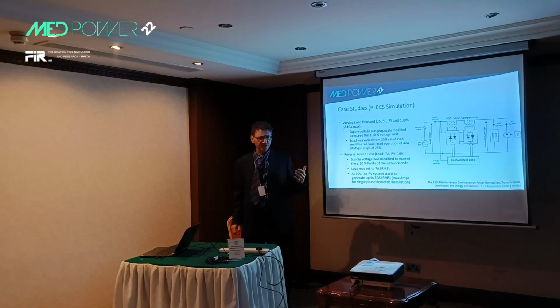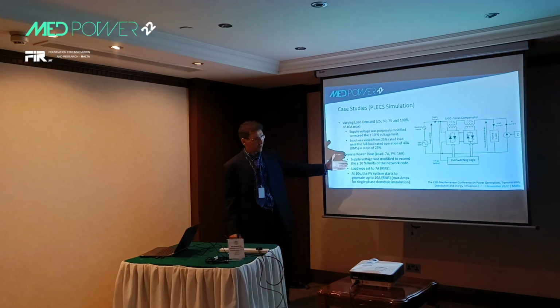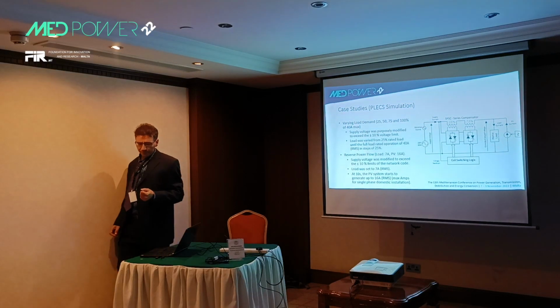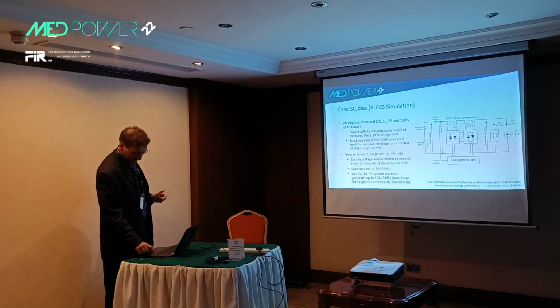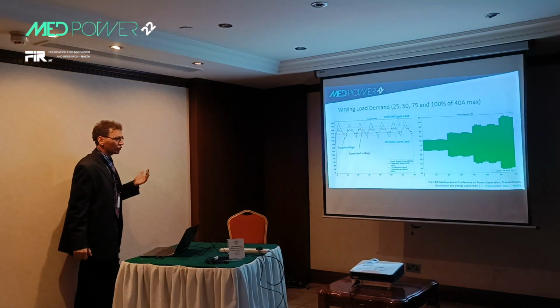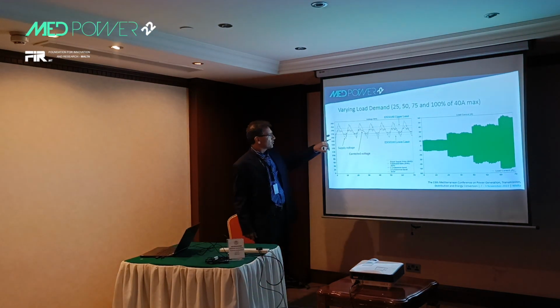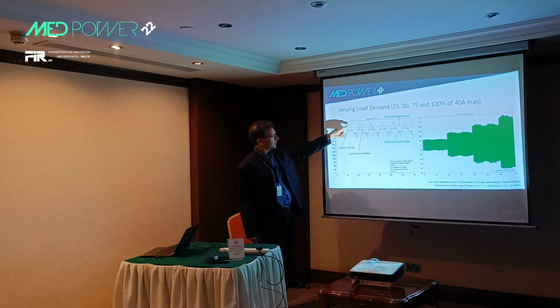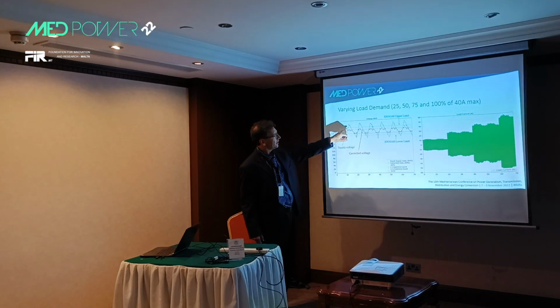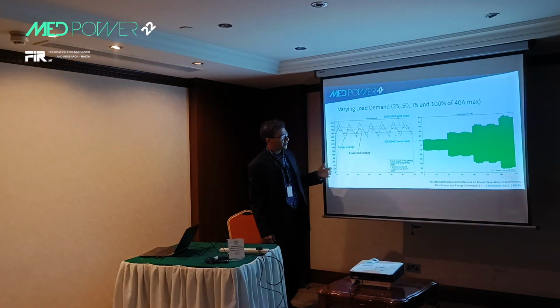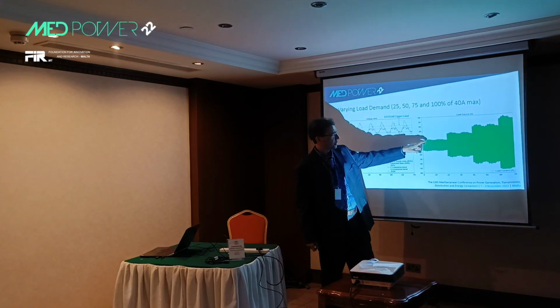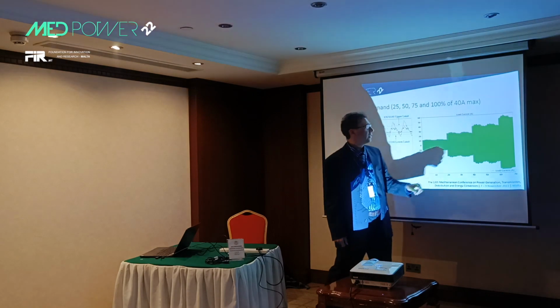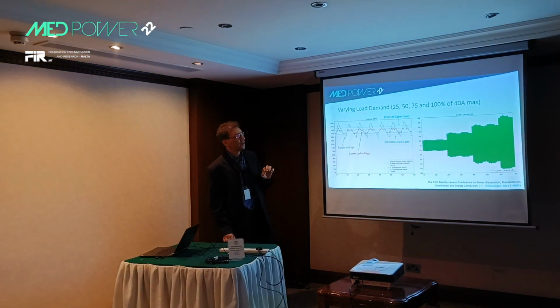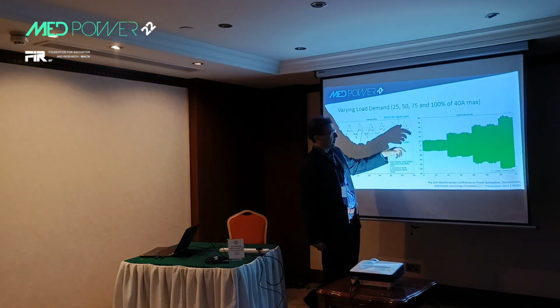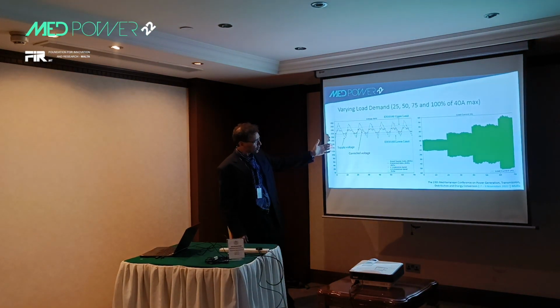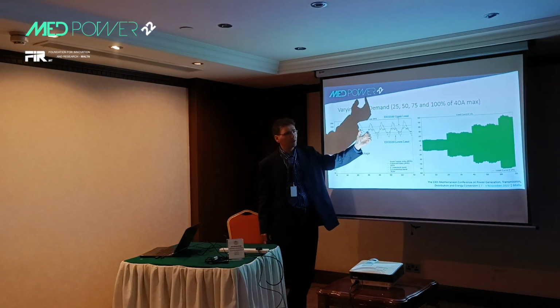And we noticed that in both cases, when we've got heavy loads, when we've got reverse power flow, the compensating circuit and the logic behind it worked in such a way that they always managed to keep the voltage within the limitations. So this is our distorted supply voltage, the green one. This red one is the voltage corrected by our series compensator. Okay, over here you can see the load current. So here we're at 25, 50, 75, and 100% of the 40 amps RMS, okay? This is showing you the peak value of the current, not the RMS. So as you can see, the correction is completely load independent.